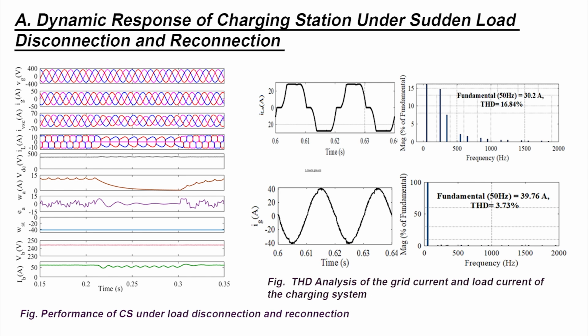So here we need to maintain grid currents sinusoidal, and we can see under load unbalancing the grid currents are balanced. On the right side, as these chargers behave as non-linear loads, the total harmonic distortion of the charger is around 16.84. However, the grid current THD is maintained within IEEE 519, which requires less than 5%. Here it is 3.73.